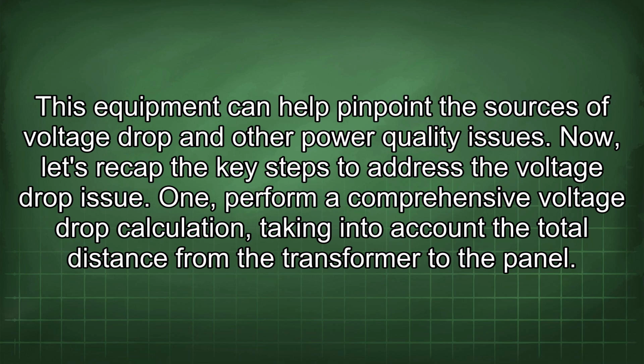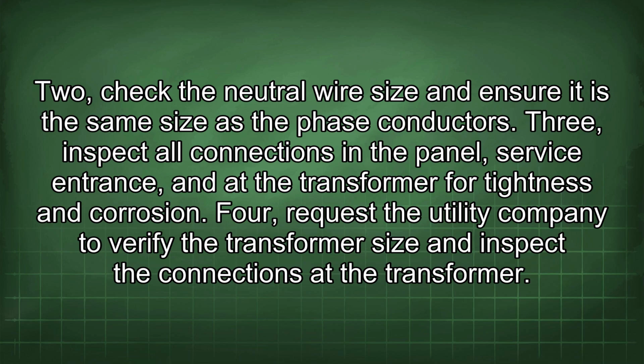Now let's recap the key steps to address the voltage drop issue. 1. Perform a comprehensive voltage drop calculation, taking into account the total distance from the transformer to the panel. 2. Check the neutral wire size and ensure it is the same size as the phase conductors. 3. Inspect all connections in the panel, service entrance, and at the transformer for tightness and corrosion. 4. Request the utility company to verify the transformer size and inspect the connections at the transformer.